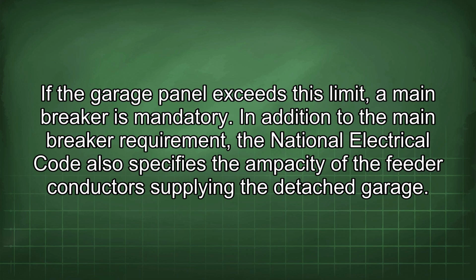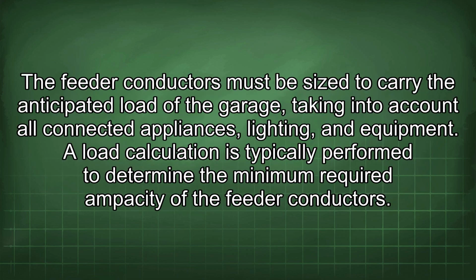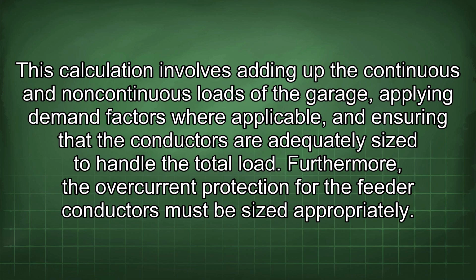In addition to the main breaker requirement, the National Electrical Code also specifies the ampacity of the feeder conductors supplying the detached garage. The feeder conductors must be sized to carry the anticipated load of the garage, taking into account all connected appliances, lighting, and equipment. A load calculation is typically performed to determine the minimum required ampacity of the feeder conductors. This calculation involves adding up the continuous and non-continuous loads of the garage, applying demand factors where applicable, and ensuring that the conductors are adequately sized to handle the total load.